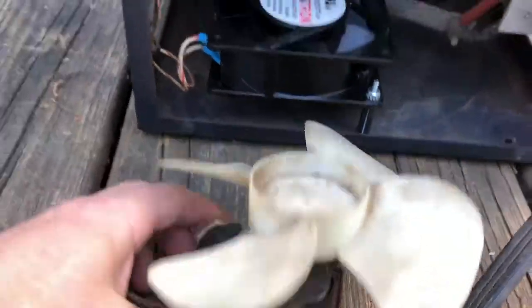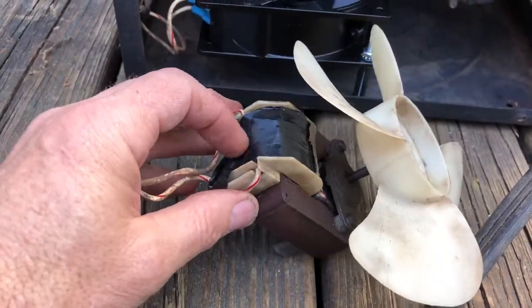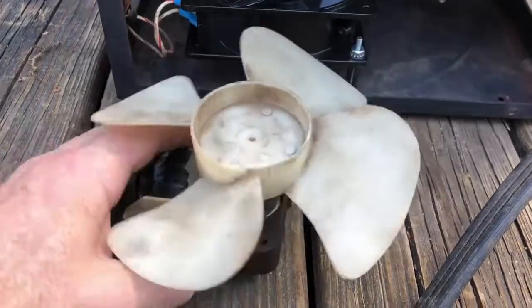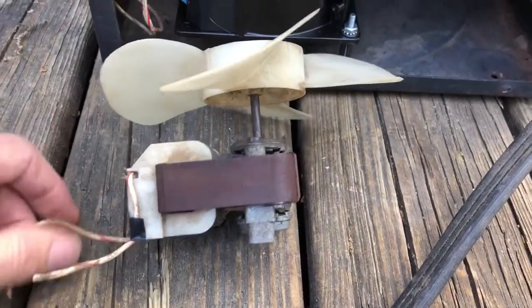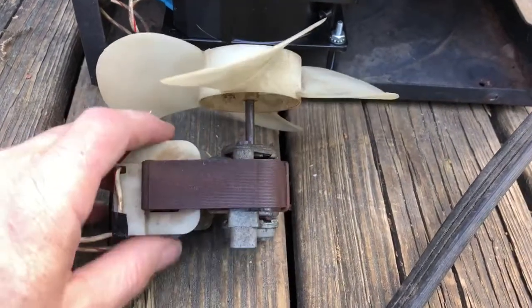I took the fan out, took it apart, and found out the leads going into the winding on this motor were bad — old, corroded, broken. I mean, it was in really bad shape. I tried to remedy the situation by soldering the wires back in, but it was no good.